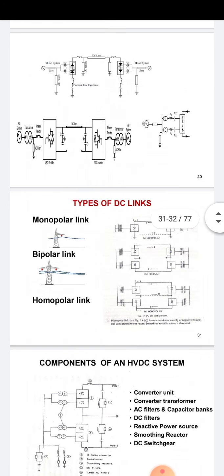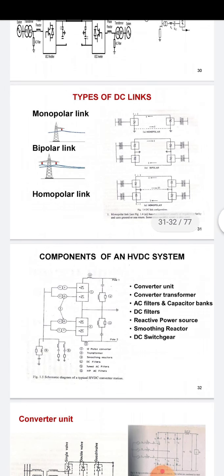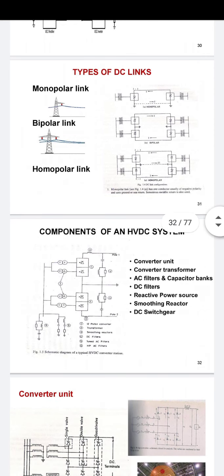Types of DC links: a monopolar link has only one conductor, usually of negative polarity, using ground or sometimes metallic return. A bipolar link has two conductors — one positive and one negative — with each terminal having two sets of converters of identical rating connected in series on the DC side. A homopolar link has two or more conductors all of the same polarity, always operated with ground or metallic return.